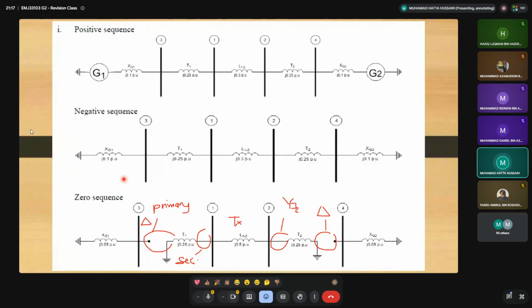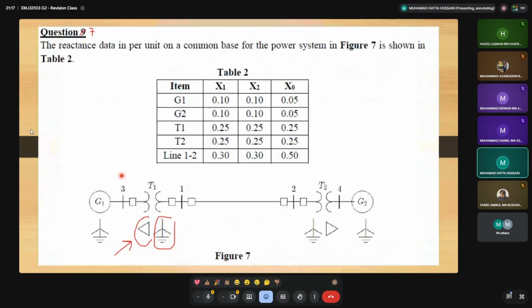But the most important thing, if you want to draw the zero sequence, you need to take a look back at your single line diagram. Because for the zero sequence network, you must consider all these connections: star connected to ground, delta here, star connected to ground. You must consider these.